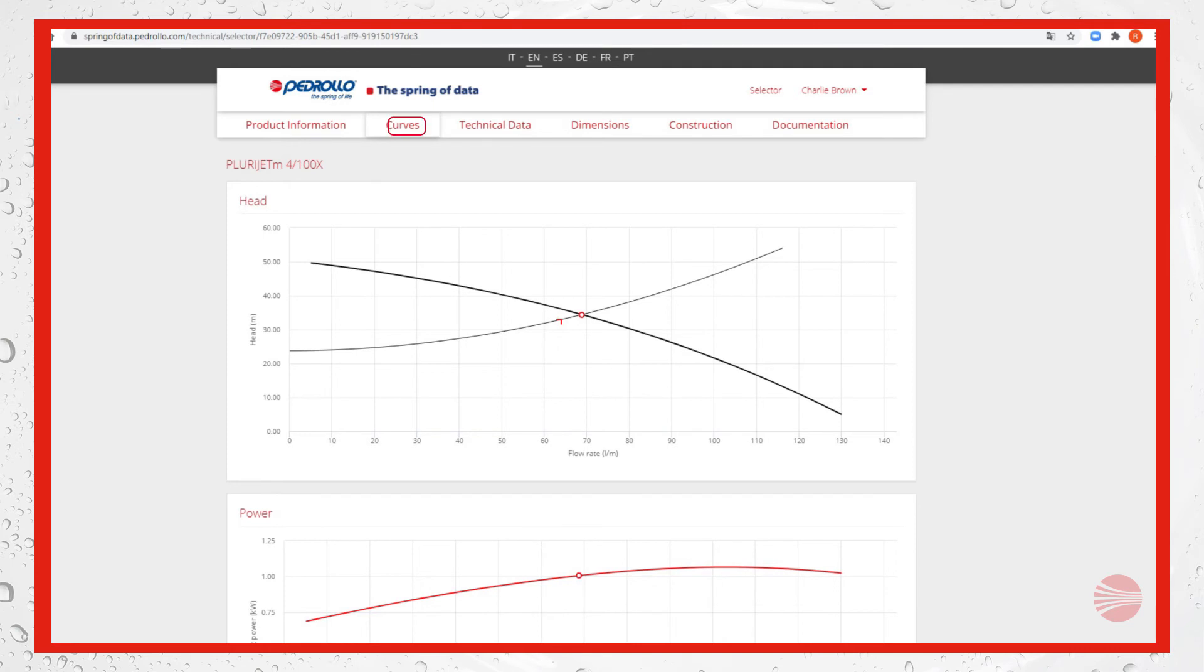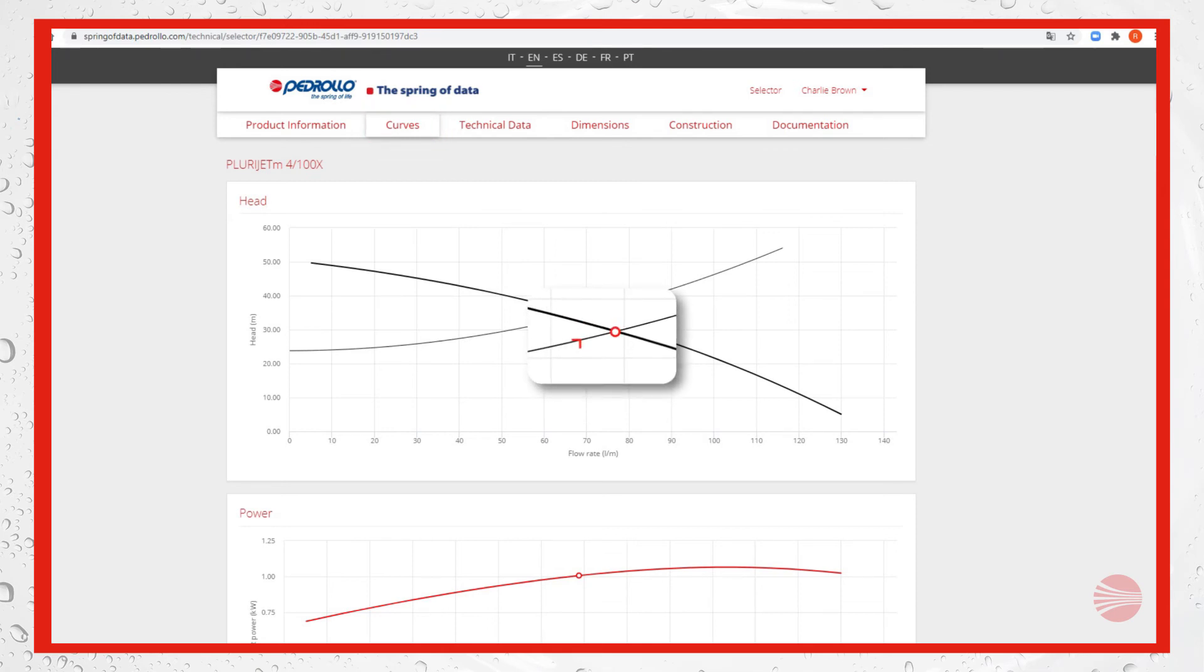On curves we can see the head curve of the electro pump as well as the system head curve. The upside down L is again the required duty point, while the round spot, the crossing of the two curves, is the actual duty point.